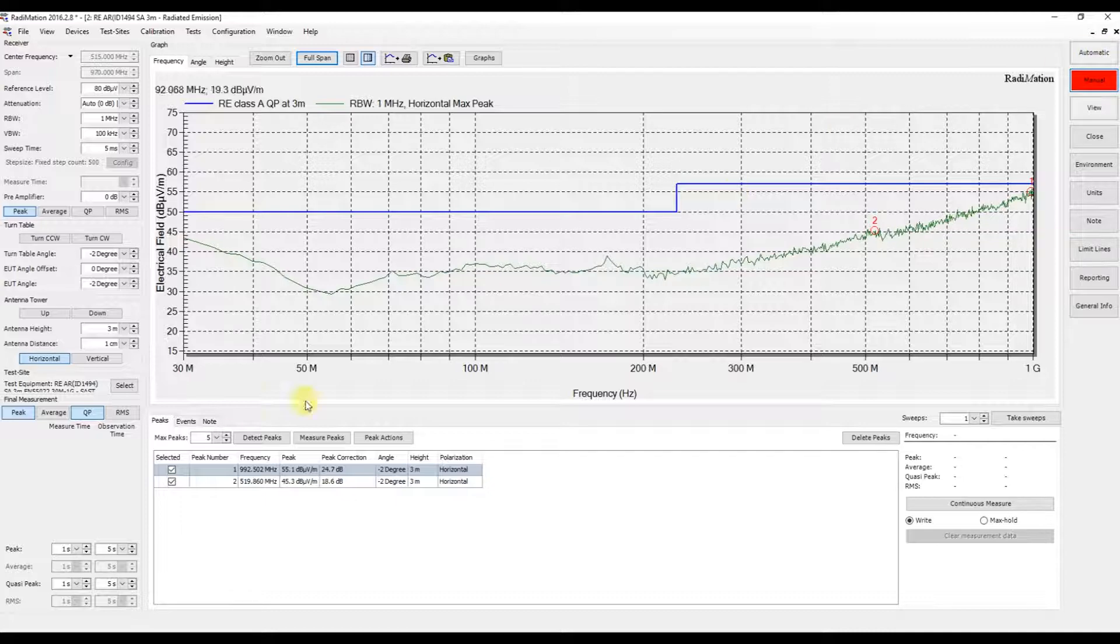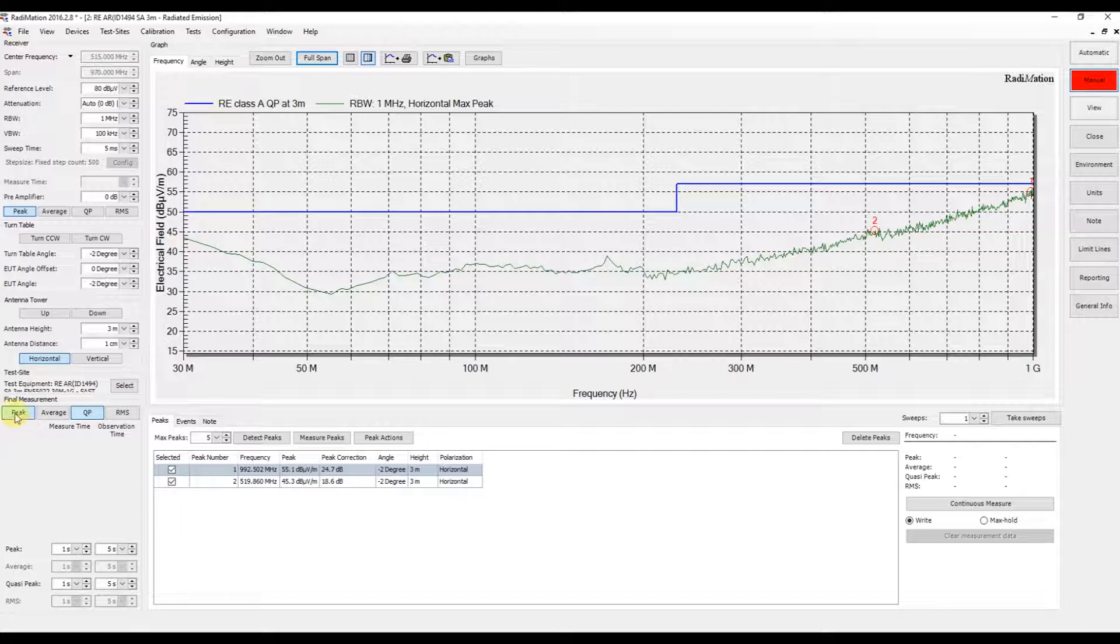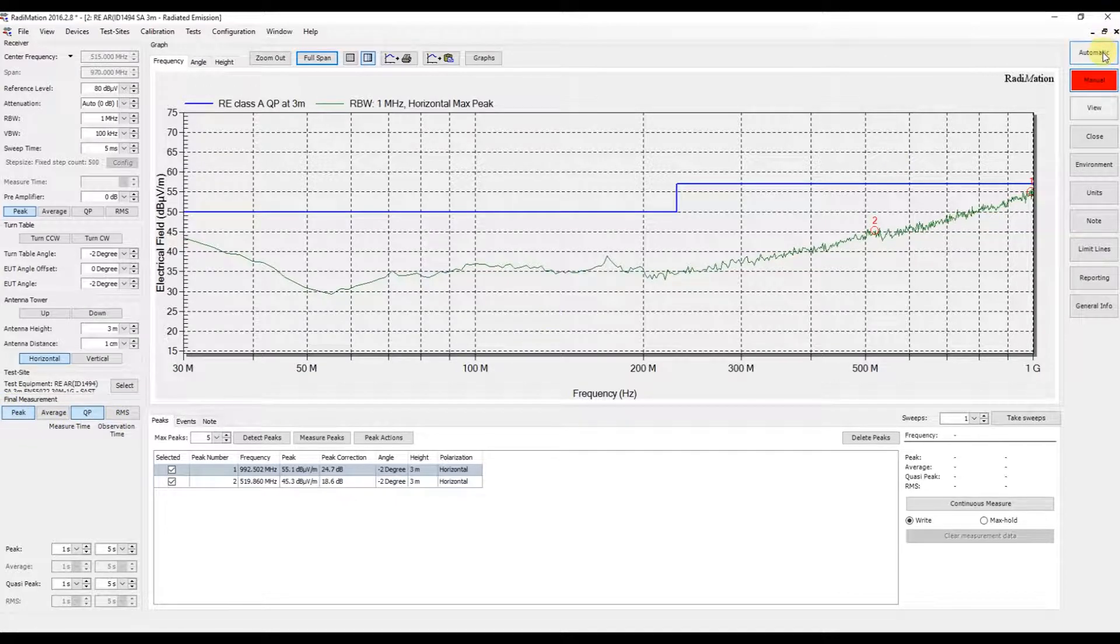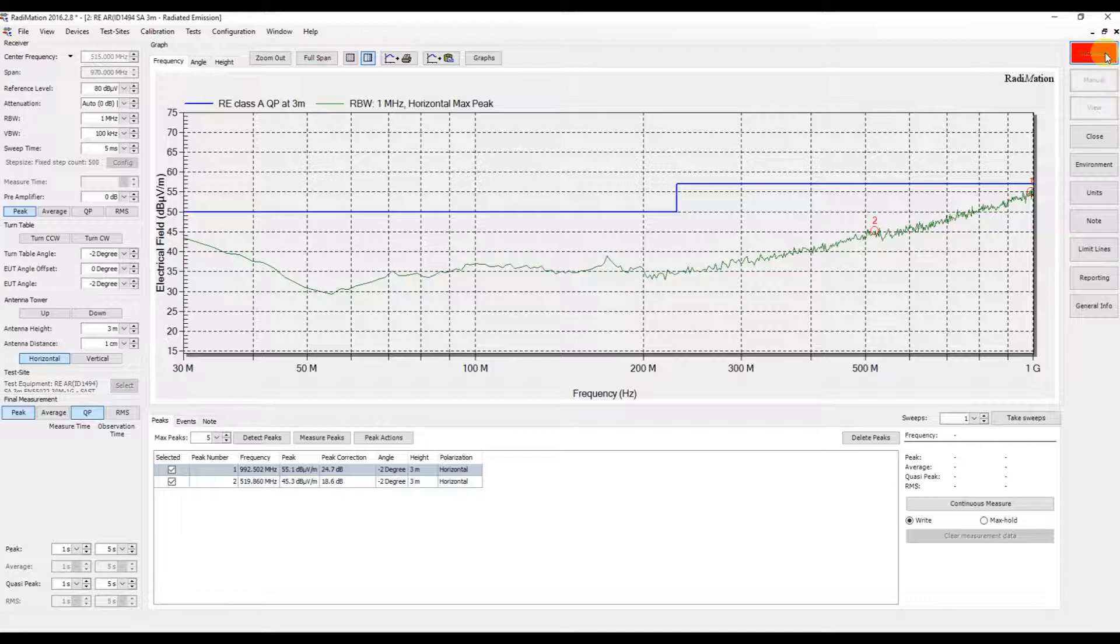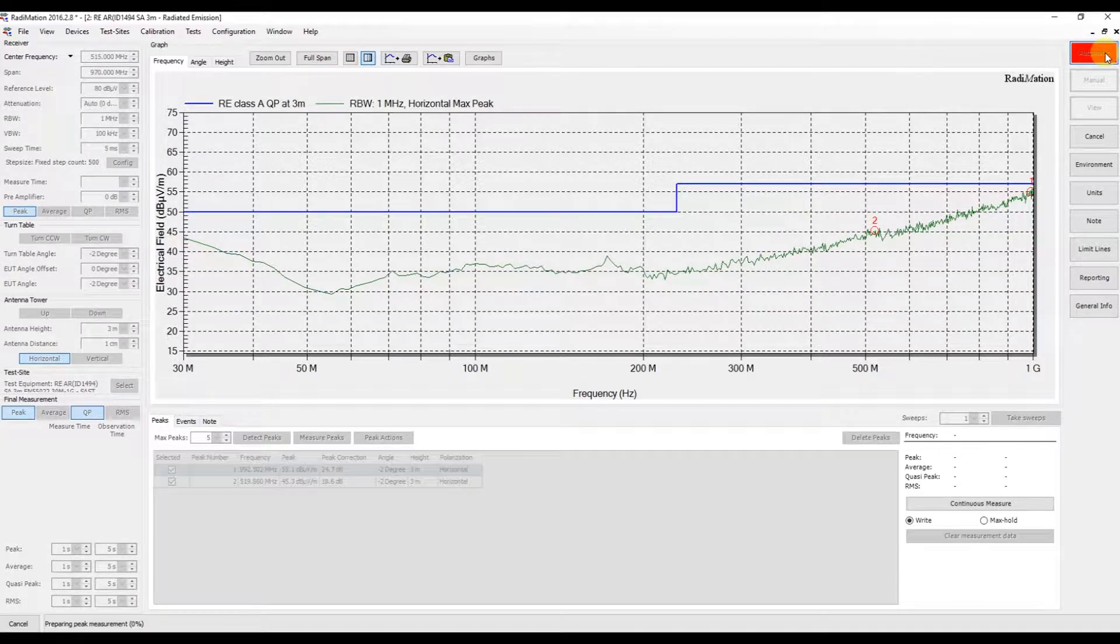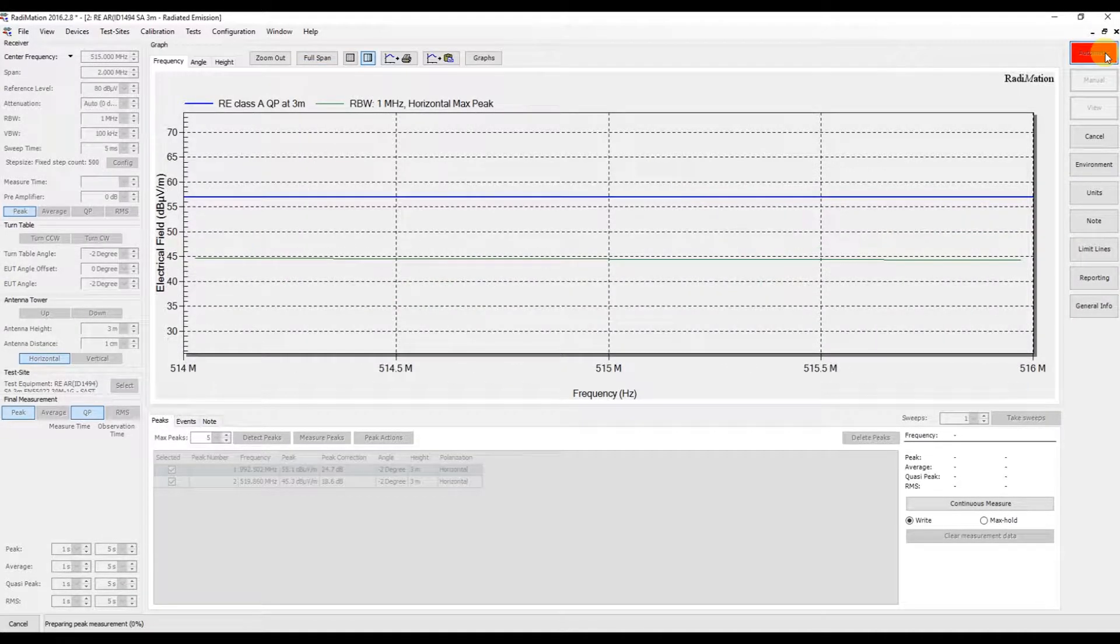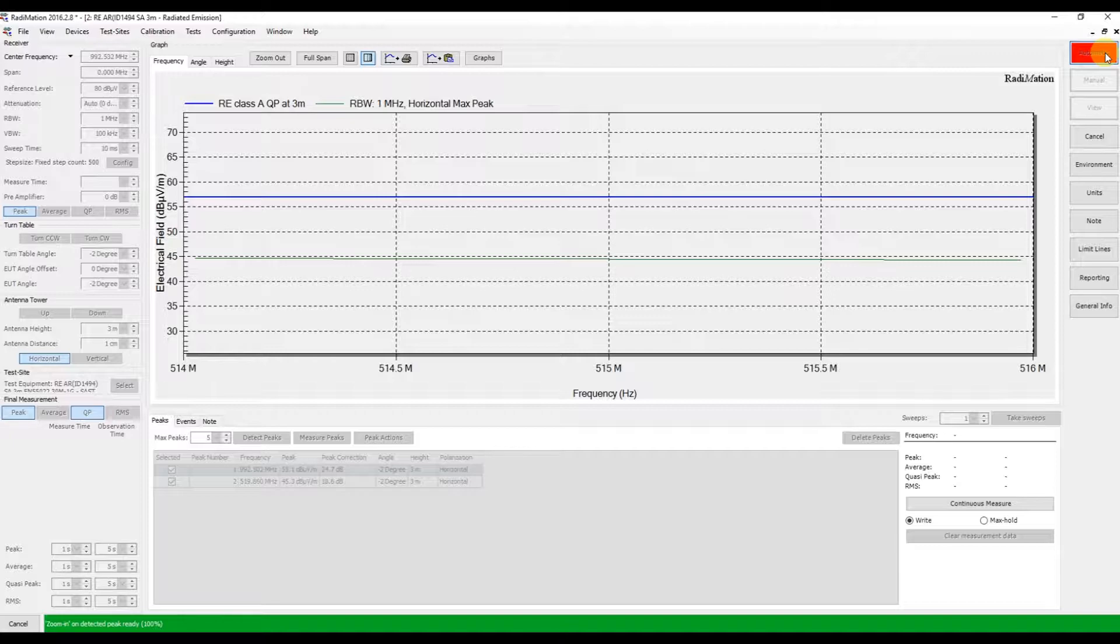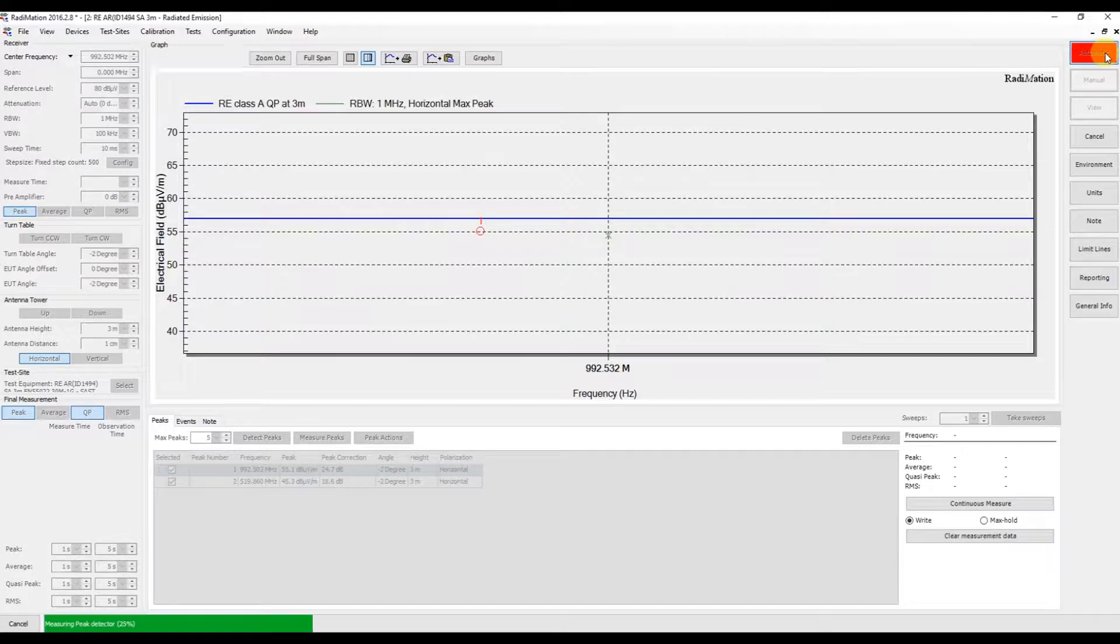We can automatically have them measured as the final measurement according to the test configuration in the TSF. In this case, peak and quasi-peak detectors will be used. We press automatic and the automatic measurement starts.